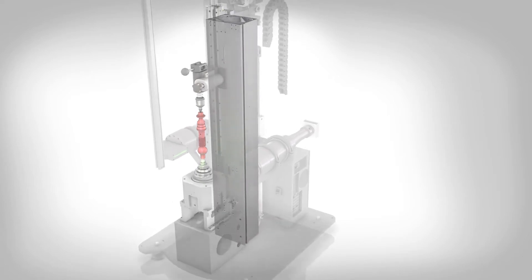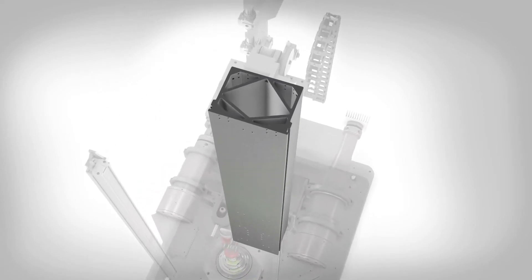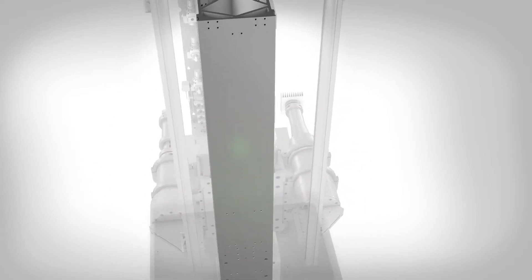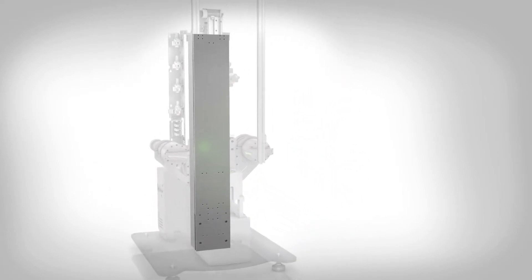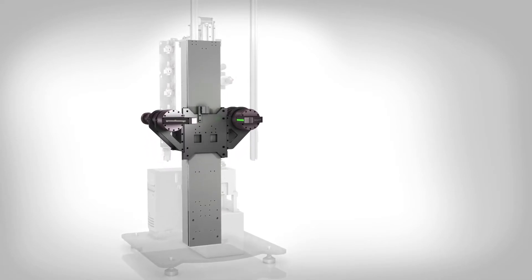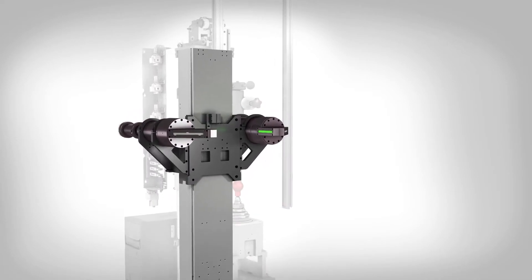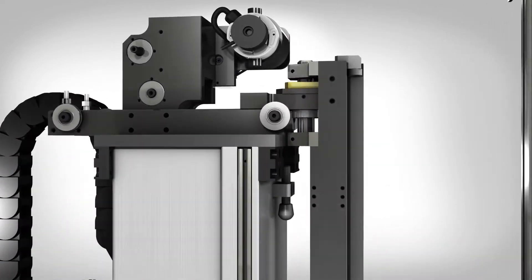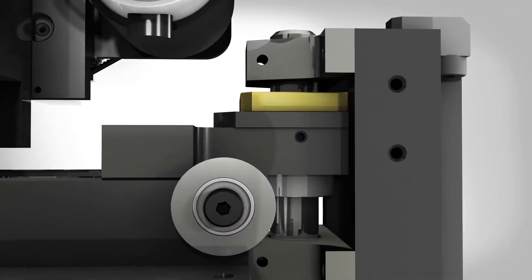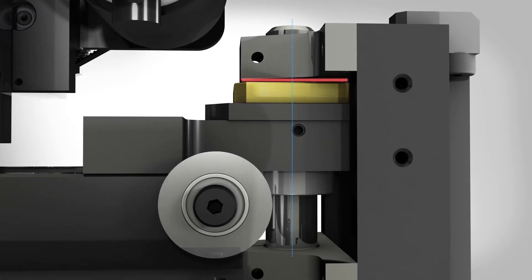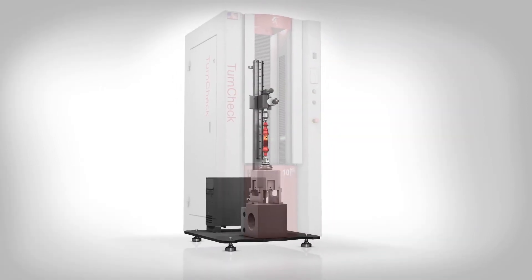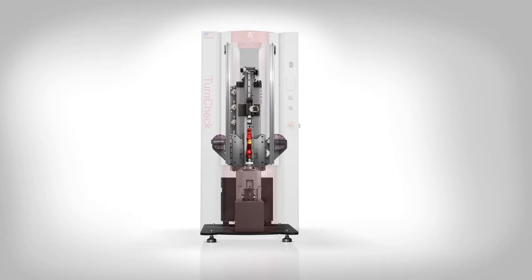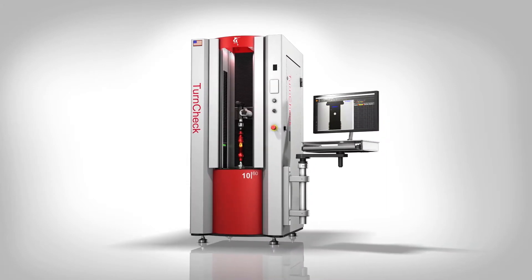An extruded aluminum column with an internal lattice provides highly rigid support for the optical motion assembly. A patented bearing weight design isolates the optical motion from the effects of thermal expansion. The tailstock beam is constrained radially but remains compliant in the linear axis, decoupling the thermal expansion of the aluminum support column from the steel tailstock. Each carefully selected material is monitored and compensated to maintain thermal stability and long-term repeatability.